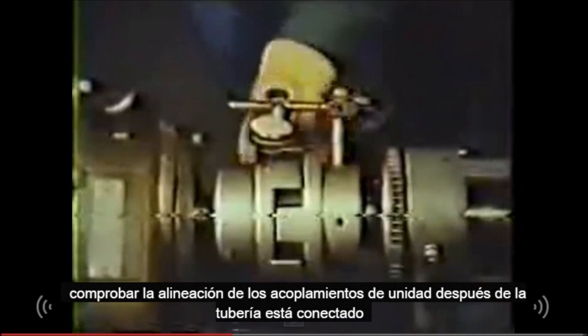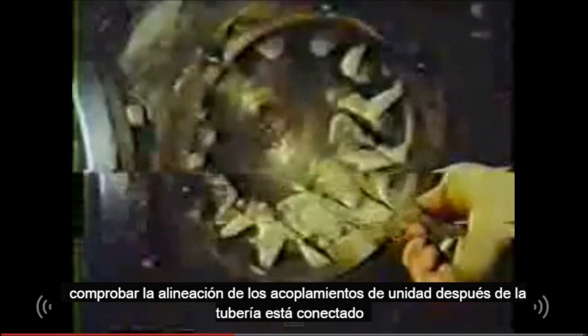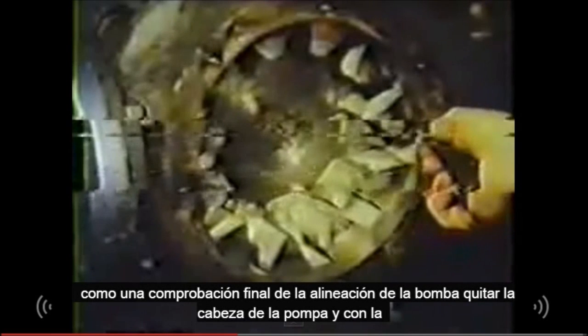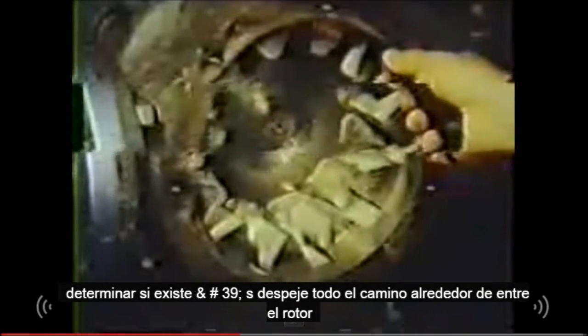Check the alignment of the drive couplings after the piping is hooked up. As a final check on pump alignment, remove the head of the pump and with a thickness gauge, determine if there is clearance all the way around between the rotor and casing.